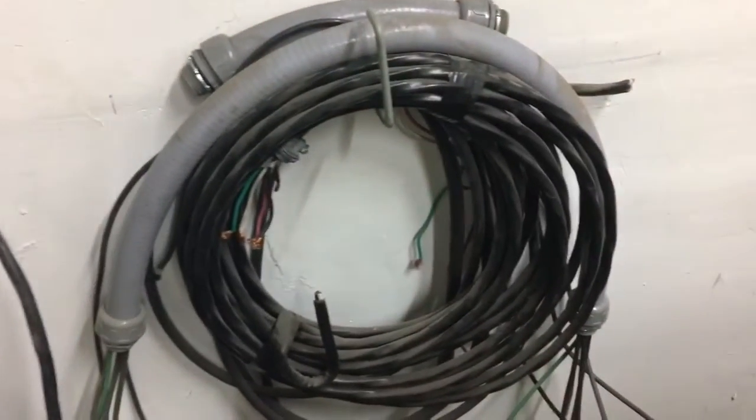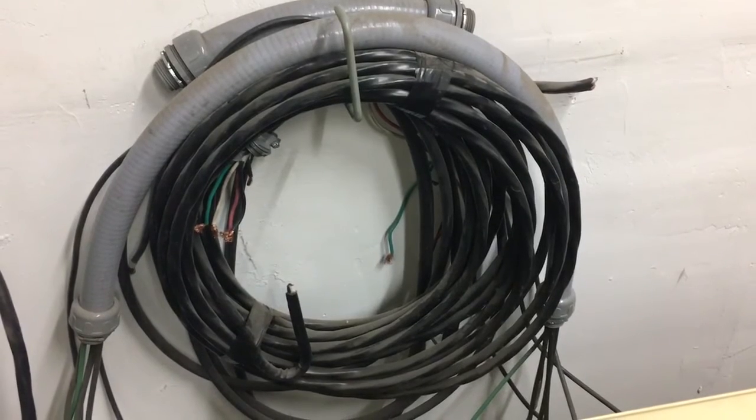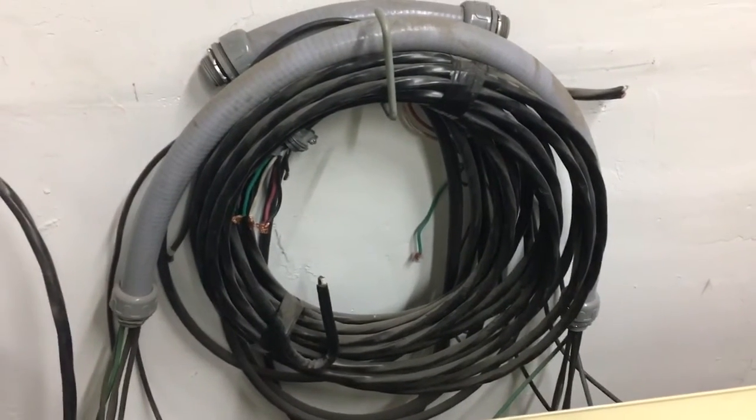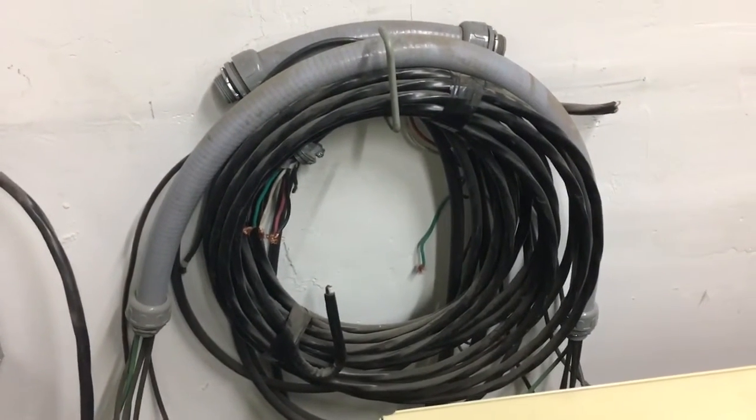replacing this wire several times — because Danny Florensic, one of the two brothers that runs Phoenix Phase Converters, said it was too small — we finally switched electricians. We hired a different electrician who came in and said that the transformer Phoenix Phase Converters sold us was in fact grossly undersized.